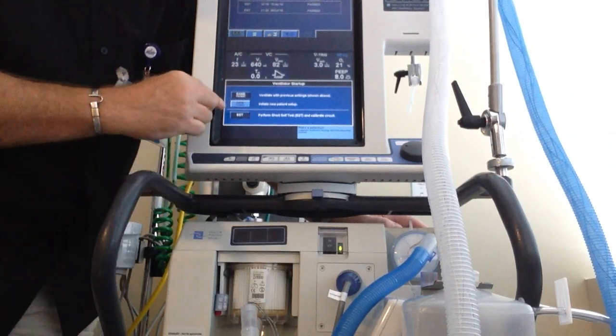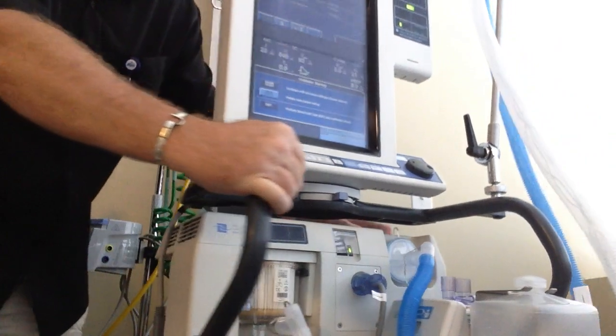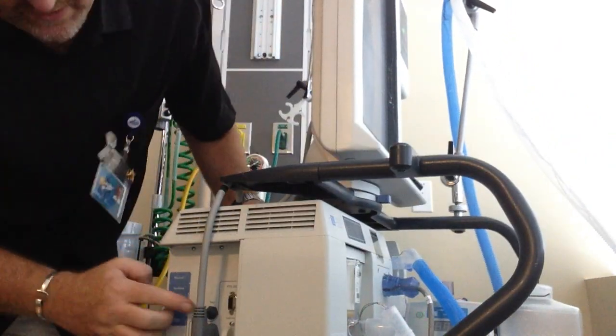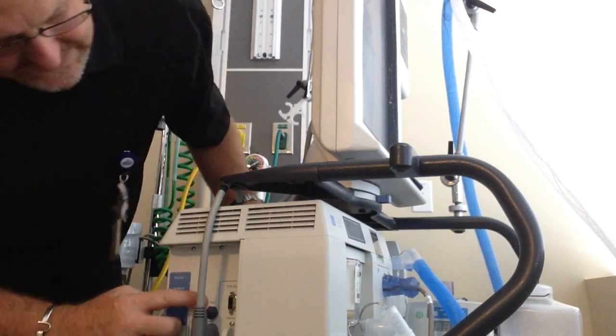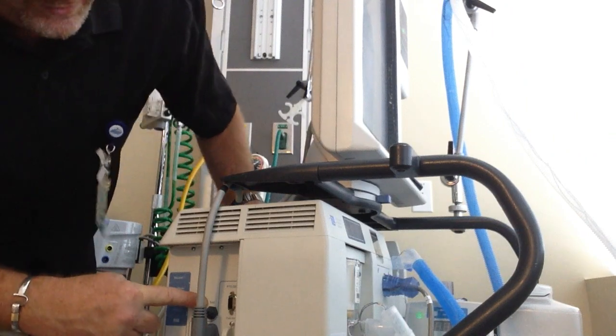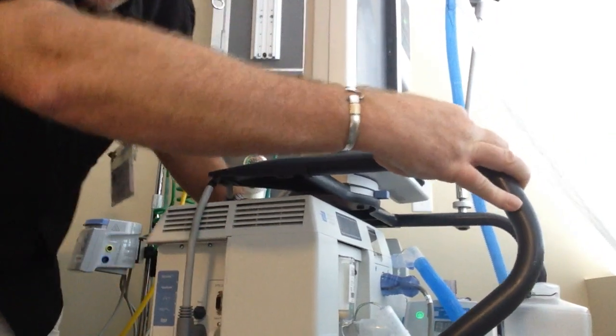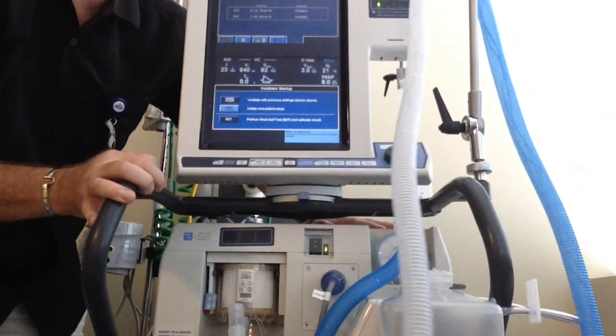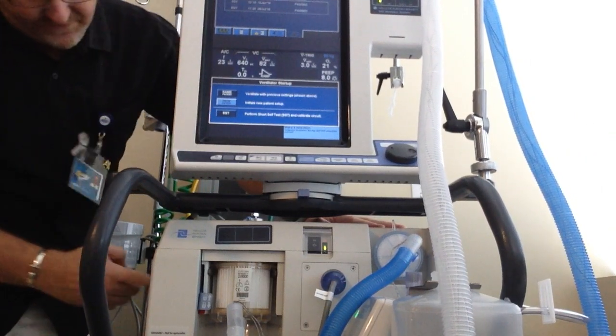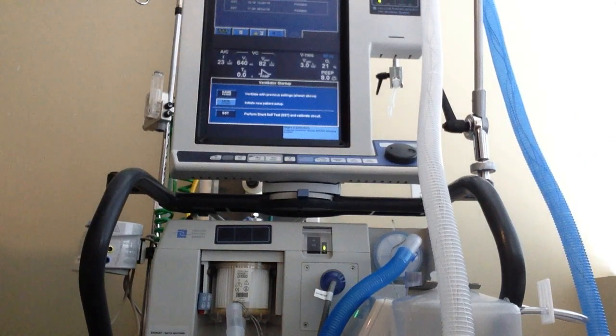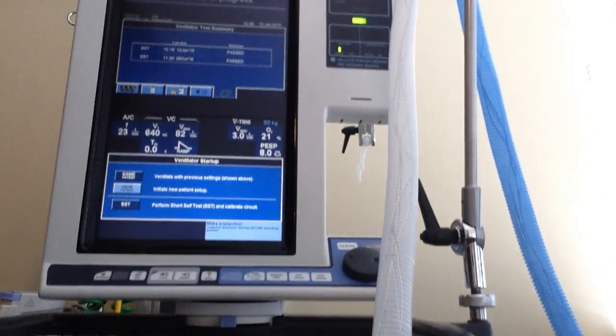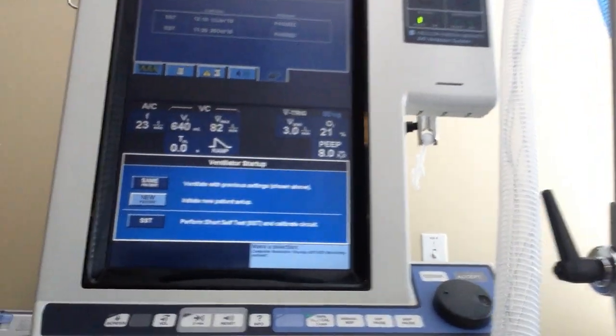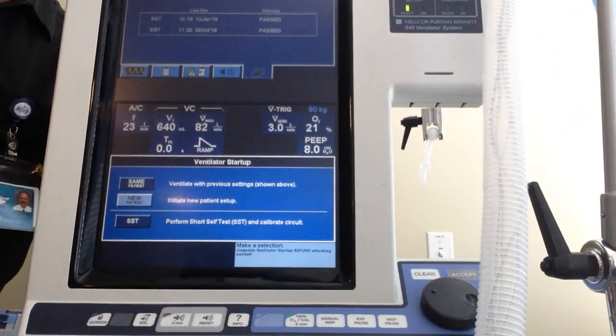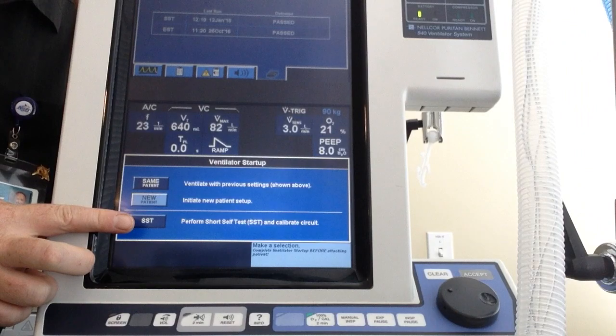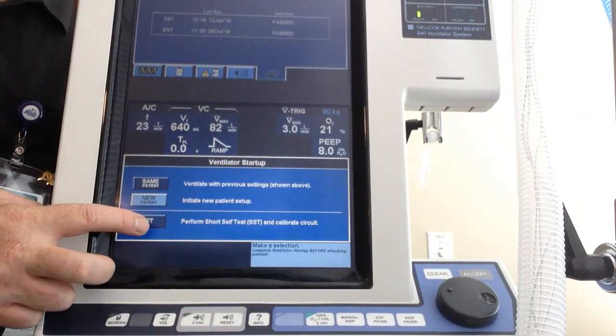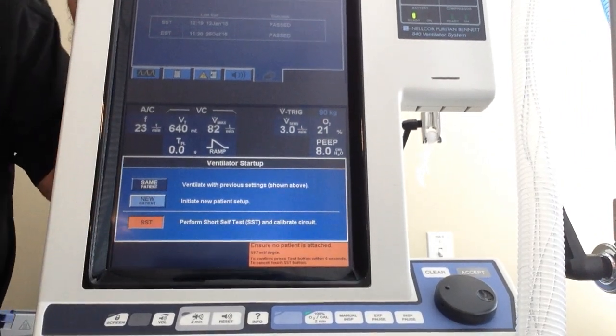Now, when I press this box, I have about 10 seconds to press a button on the side, which is right here behind the power cord. This says test, T-E-S-T. So when you're in lab, look at it. So once you turn on the Puritan Bennett 840, you then press this button, and you have 10 seconds to press the button on the side. So I'm going to reposition the camera to get you a little better view. There. You see how it says SST? I am then going to press that, and then come down here and press on the side.